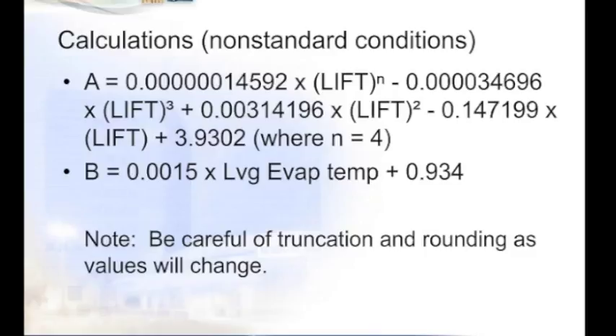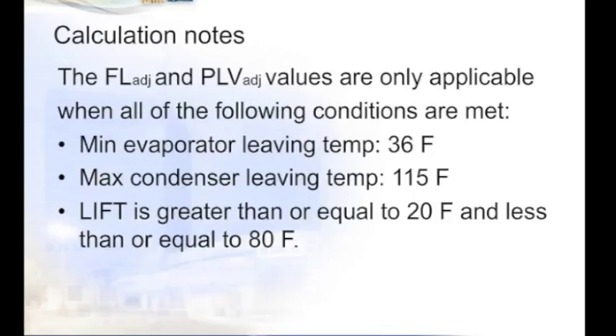Some of the notes that are important as to what these calculations apply to are the full load adjusted and the part load adjusted values are only applicable when all of the following conditions are met. The minimum evaporator leaving temperature is 36 degrees. The maximum condenser leaving fluid temperature is at 115 degrees maximum. And the lift, which we defined, is greater than or equal to 20 degrees and less than or equal to 80 degrees as calculated in the formula. So anything outside of those ranges do not meet that criteria or standard.